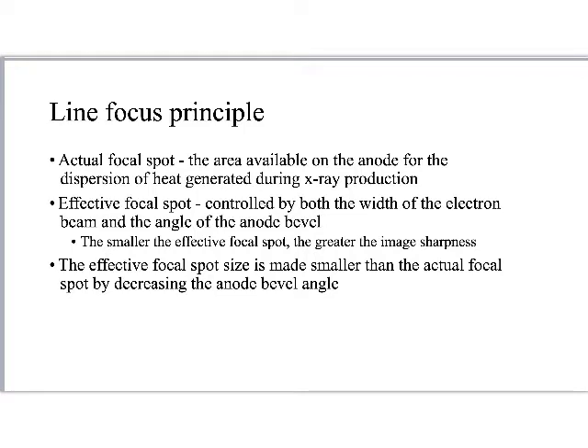I will repeat that because that's a big takeaway from this section. But first, let's talk about this line focus principle. Some of the terminologies we need to be aware of is that there is an actual focal spot. The actual focal spot is an area available on the anode for the dispersion of heat generated during x-ray production. It's the area that the electrons are focused on on the anode in order to produce x-rays. Sometimes technologists will talk about, or on the test they'll talk about, the focal track.